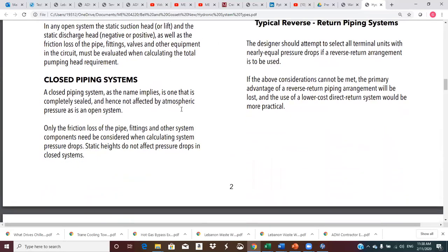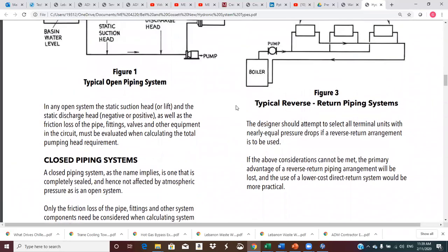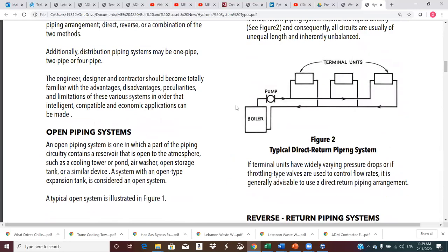Okay. A closed piping system is one that's completely sealed. In other words, it's encased in pipe all the way around. And so on these, it's only friction losses in fittings and components. There's no static head to worry with. So it's a significant difference between these two types of systems.